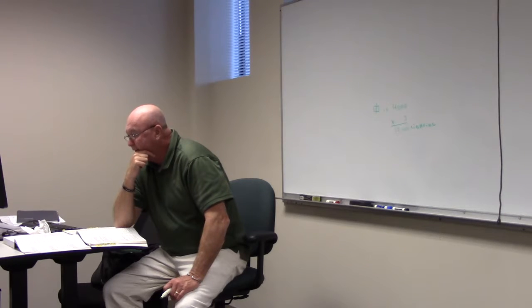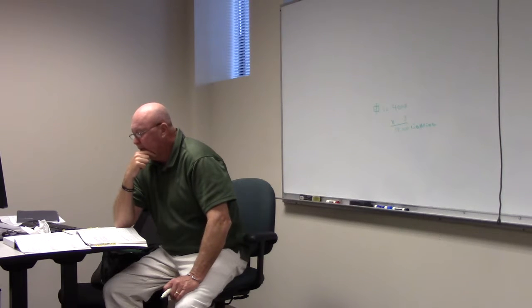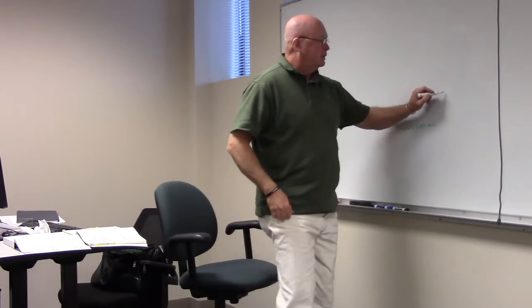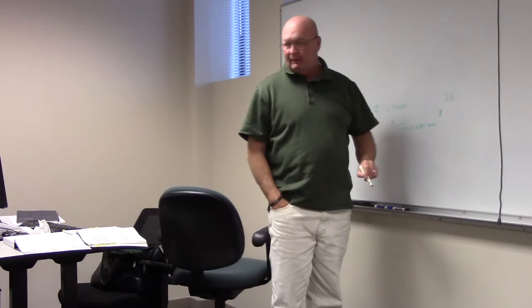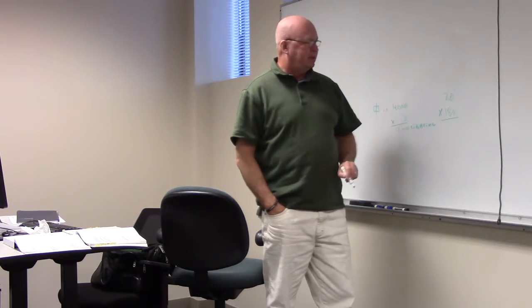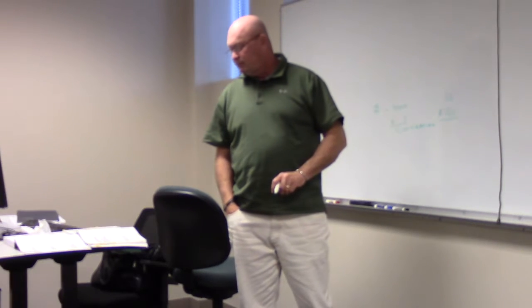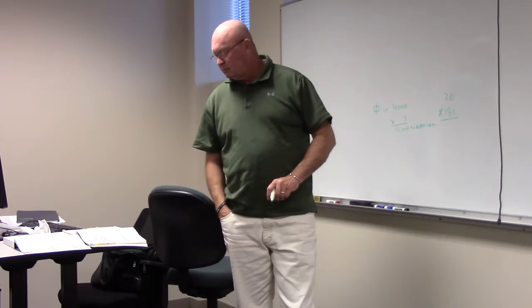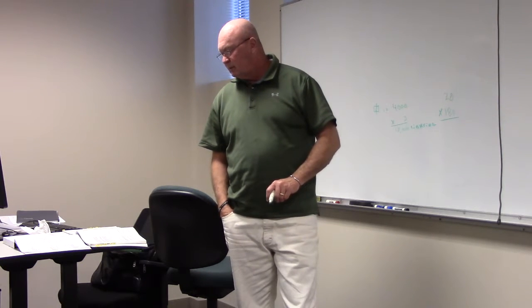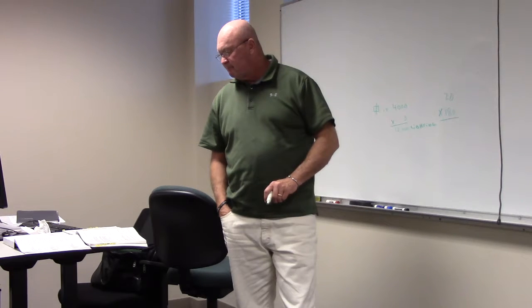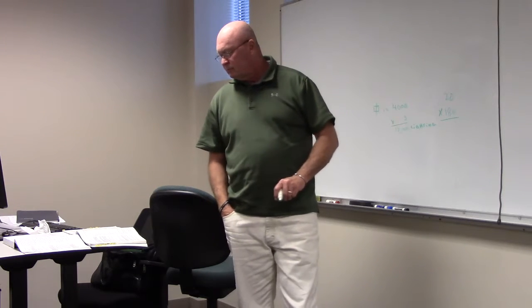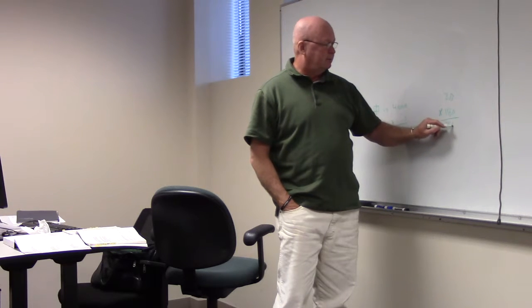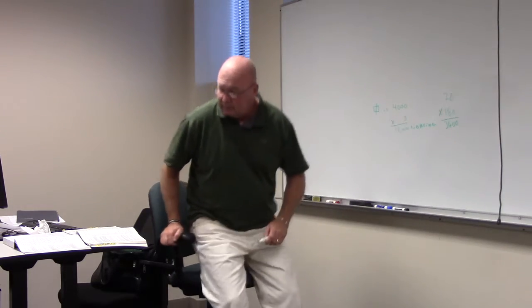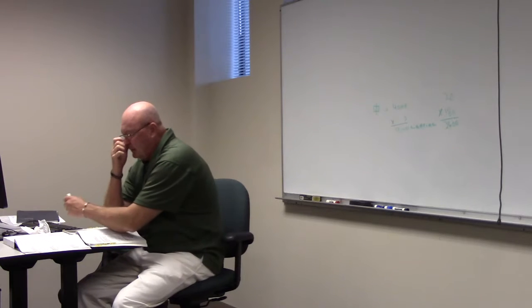We had 2 floor receptacles. So how many outlets is that? Four plus 14 plus 2. 20. So we've got 20 outlets. And an outlet is how many volt-amps each? 180. So we're going to multiply 20 times 180, and we're going to get how much? 3,600? Is that right? Yes. Okay.